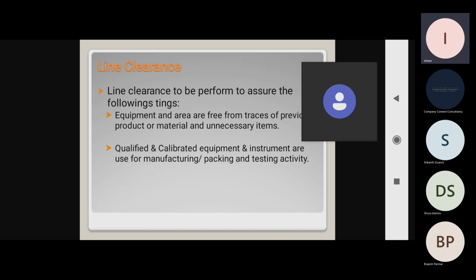Another thing is we have to verify the qualified and calibrated state of the equipment and instruments used in manufacturing and packing activities. Why is this required? As discussed earlier, it's a clause of the guidelines that we have to verify the qualification and calibration of the equipment and instruments that we are using for manufacturing, packing, and testing of that particular product.